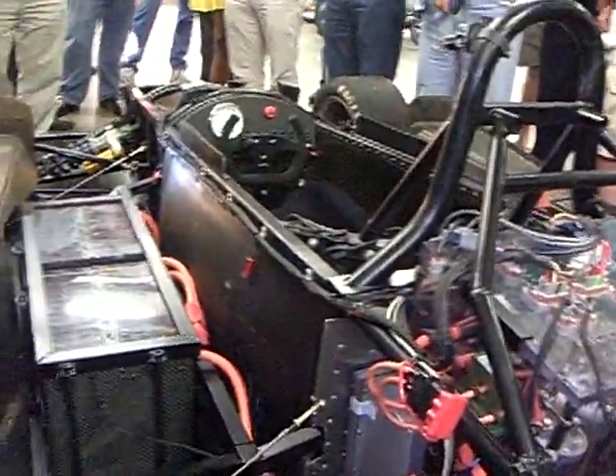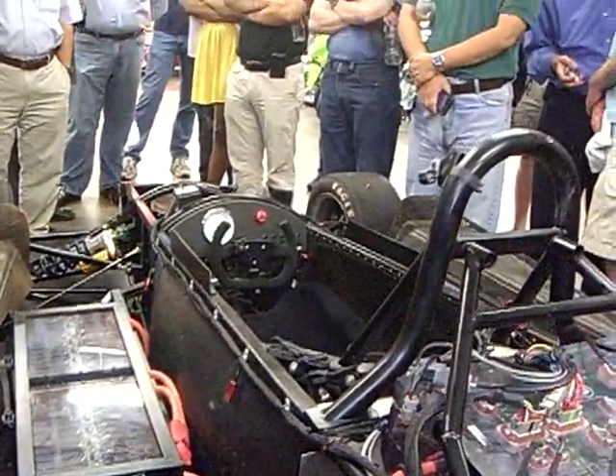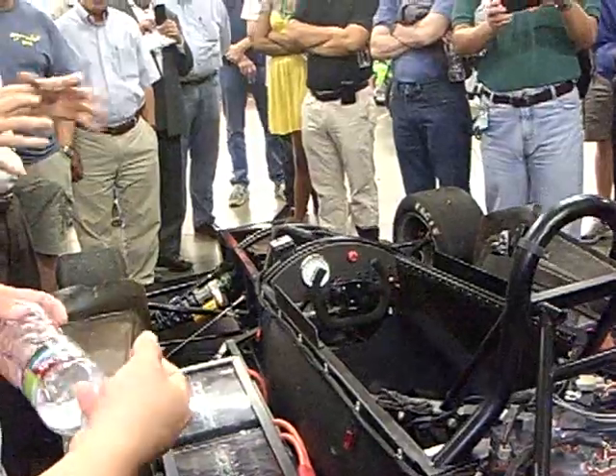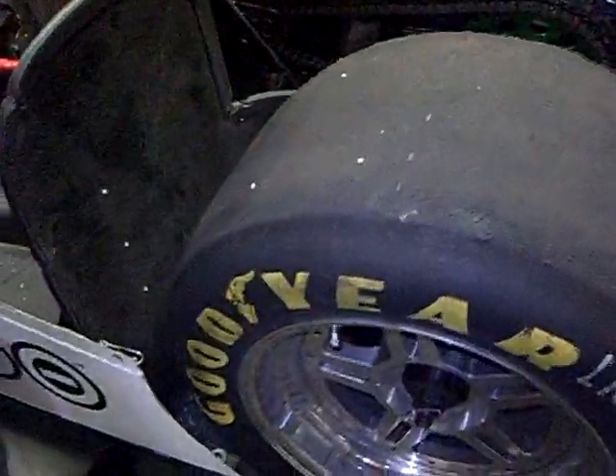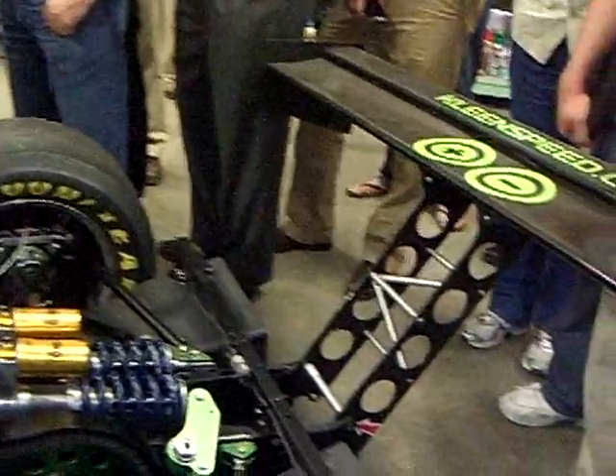Polycarbonate is notorious for impact resistance. It's very insulating, very dielectric, and also very machinable. So we can machine polycarbonate, and in doing so, we preserve the accuracy and precision of these enclosures, because they all need to be as equal as possible, because the cells are the same. We use 3 methods of building the box. We join sides to sides with a cement, which chemically disintegrates and melts the polycarbonate. Then we also mechanically screw them together with bolts. And on top of that, we wrap them in carbon fiber sheets. That's what we actually patented: this process of developing carbon fiber reinforced polycarbonate.